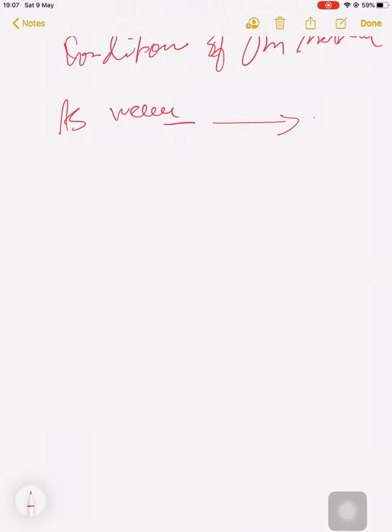But EMAT is relatively, relatively insensitive to the surface condition of the material. As waves, because if you see as waves are generated directly to the surface of the test object, the angle of generations does not depend on the inclination of the probe. Okay, less personnel training required for EMAT testing required for EMAT compared to the conventional technology.